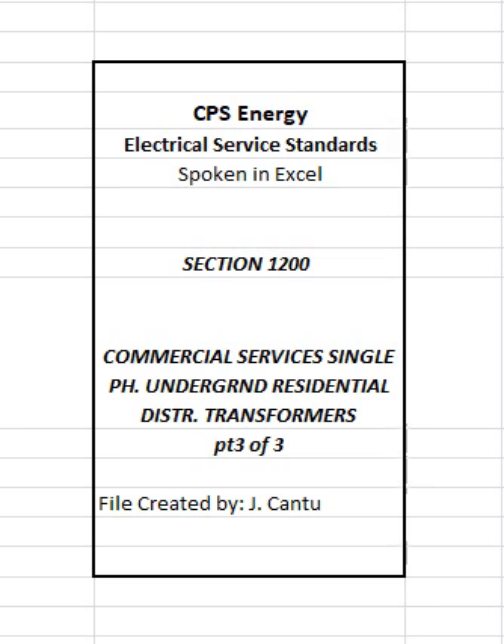1205.2 Public right-of-way. Where a new transformer or secondary enclosure is approved by CPS Energy and the AHJ to be located in public ROW, customer will furnish and install the secondary and/or service conduits from transformer and/or secondary enclosure to metering location. CPS Energy will be responsible for installing and maintaining the secondary/service conductors to the point of demarcation, POD. Customer will be responsible for installation of the service entrance conductors from the POD up to the metering location. Where CPS Energy is serving telecommunications, wireless services, traffic signals, and bus shelters, etc., then CPS Energy will install the service conductors up to the meter location.